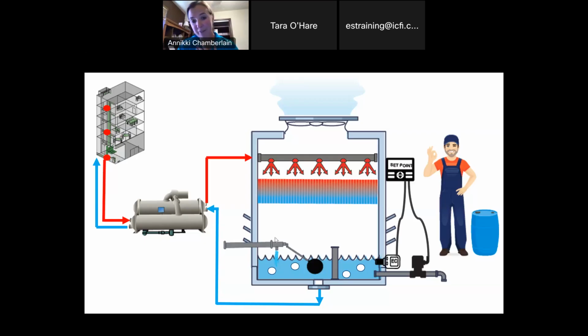What about the makeup valve? What do we see very commonly? Typically, they get stuck open, right? If that makeup valve gets stuck open, it's going to cause overflow. The tower is just going to keep filling. It's going to go over that overflow and boom, right down the drain. So again, we're definitely wasting a ton of water, and possibly wasting chemical depending on how we feed the chemical. I've not typically seen it, but you can also have your makeup valve be stuck closed, right? Then you would blow down, but you wouldn't refill. Again, that's probably more of a damage event.